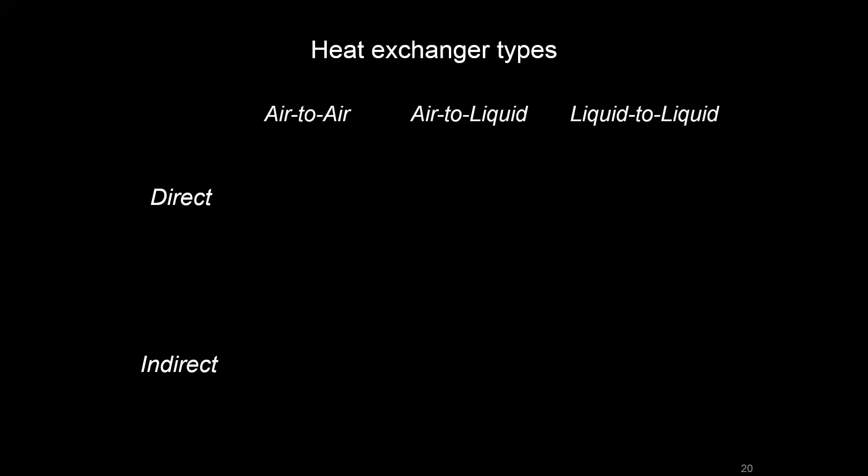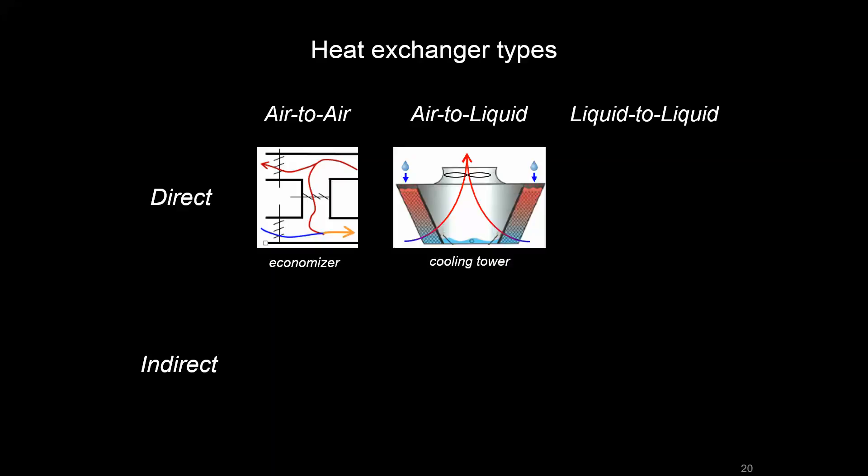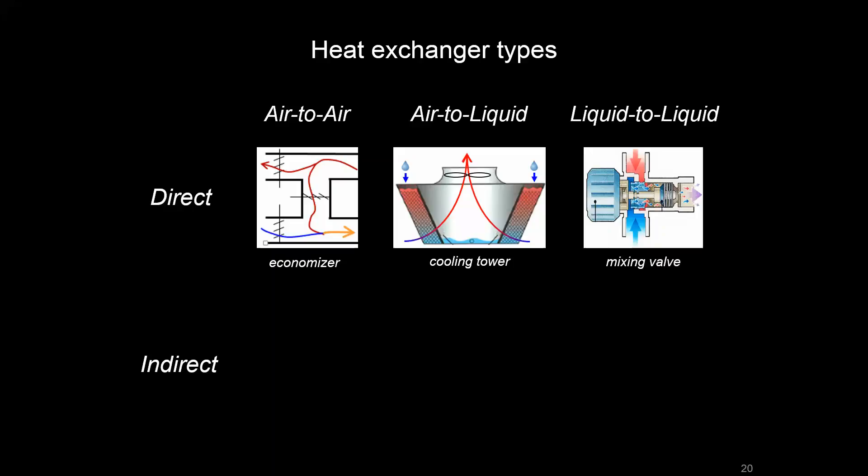And just to introduce a few more flavors, we can have different types of media associated with that heat exchange. So in an air-to-air direct heat exchange, that could be something like an economizer where you're mixing return air with outside air and providing a mixed air going to a coil or going to your space. In a direct air-to-liquid heat exchange, that could be something like a cooling tower, where water is being dropped in some fill material and air is being either blown across it or drawn up through it to then get evaporated into the air. Something like a mixing valve is an easy to understand example of a direct liquid-to-liquid heat exchanger.